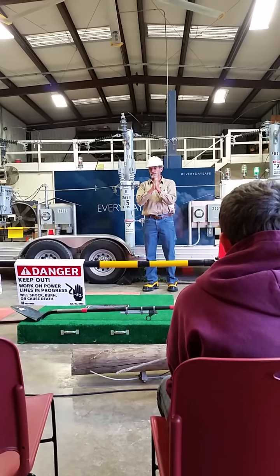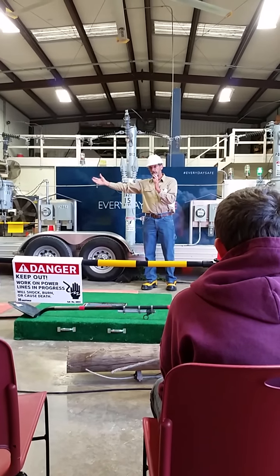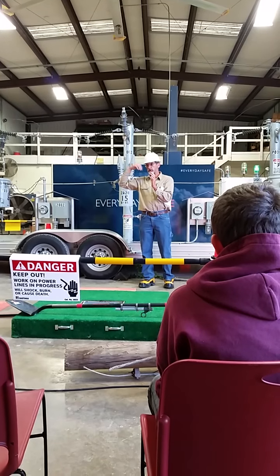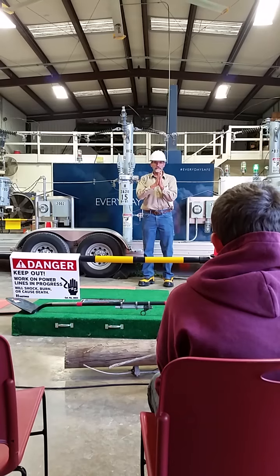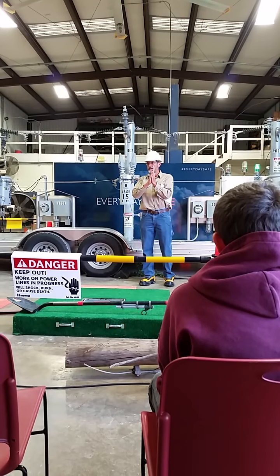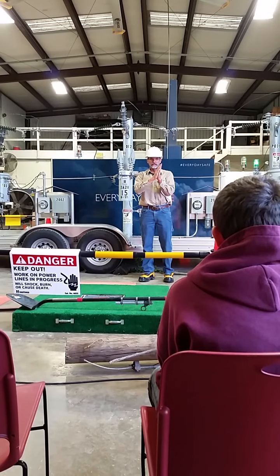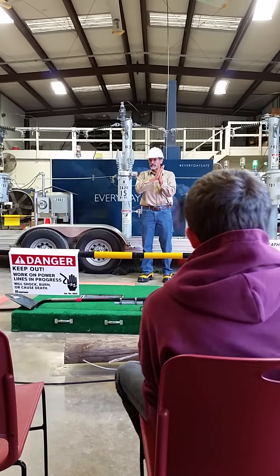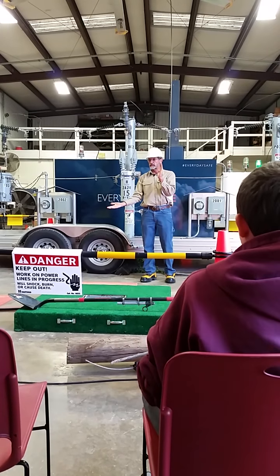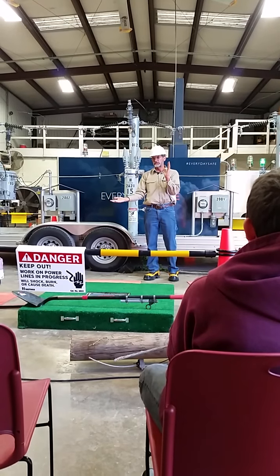No problem. But let's now change the scenario just a little bit and there's a wreck down the road, or a tree limb, or trees falling on the line that doesn't clear up. This breaker senses that fault, it opens, it closes. We're going to give it 2 more chances. It's going to open up again, it's going to close again. It's going to open up the third time on a delay, and try again. If it goes out that time, it's going to lock out. Power's off, call us. You see all those operations.